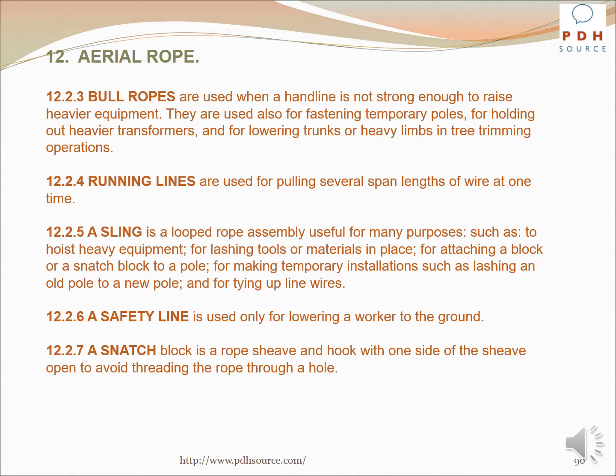A sling is a looped rope assembly used for many purposes, such as to hoist heavy equipment, for lashing tools or materials in place, for attaching a block or a snatch block to a pole, for making temporary installations such as lashing an old pole to a new pole, and for tying up line wires. A safety line is used only for lowering a worker to the ground. A snatch block is a rope sheave and hook with one side of the sheave open to avoid threading the rope through a hole.